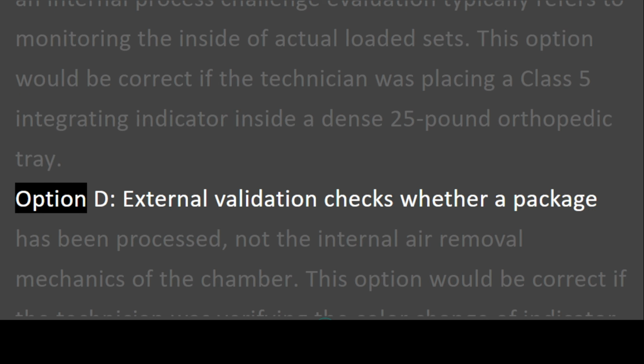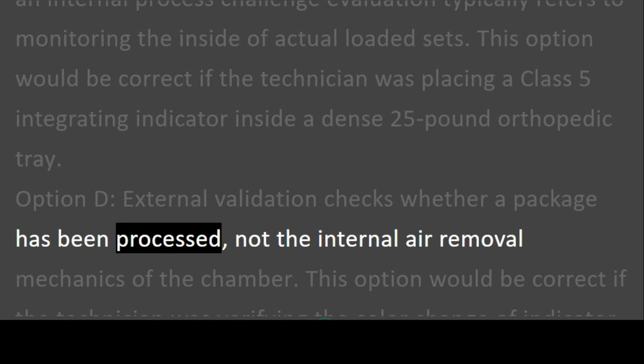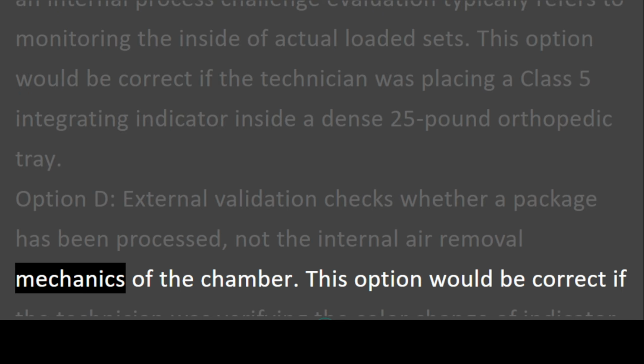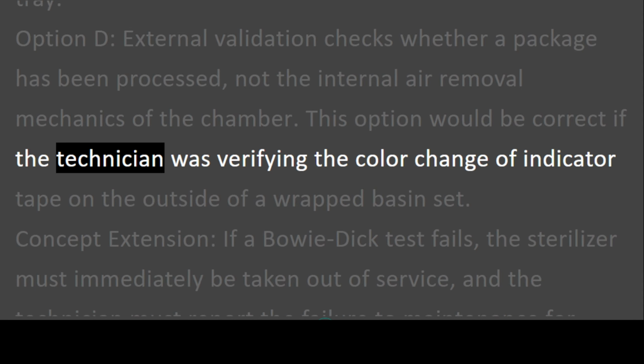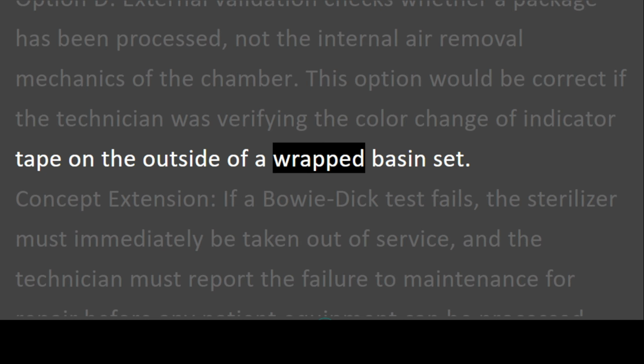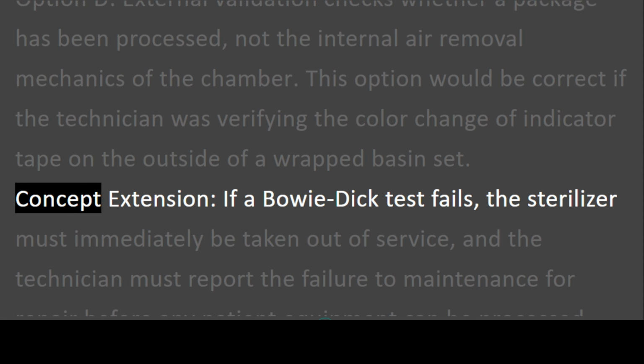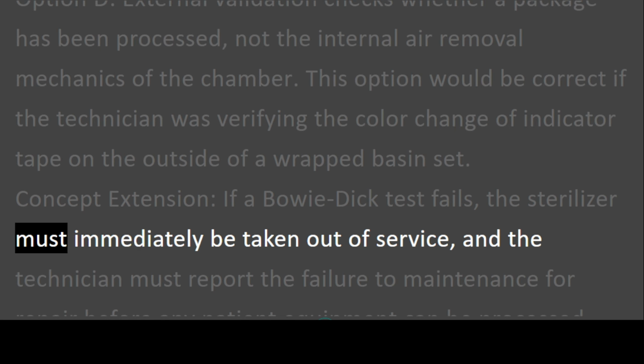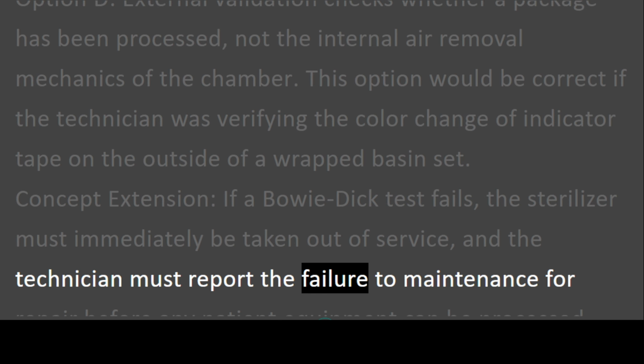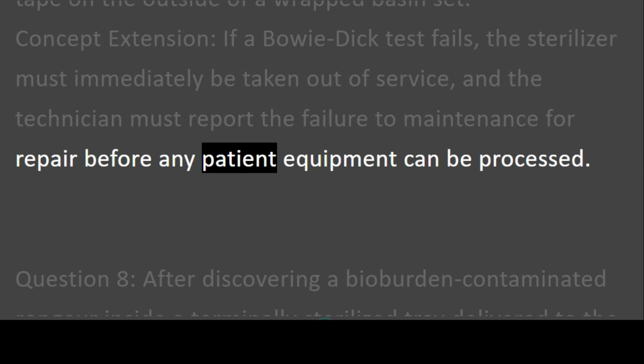This option would be correct if the technician was placing a Class 5 integrating indicator inside a dense 25-pound orthopedic tray. Option D. External validation checks whether a package has been processed, not the internal air removal mechanics of the chamber. This option would be correct if the technician was verifying the color change of indicator tape on the outside of a wrapped basin set. Concept extension. If a Bowie-Dick test fails, the sterilizer must immediately be taken out of service, and the technician must report the failure to maintenance for repair before any patient equipment can be processed.